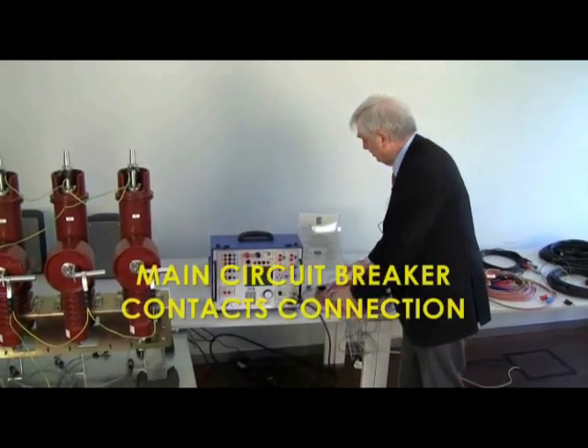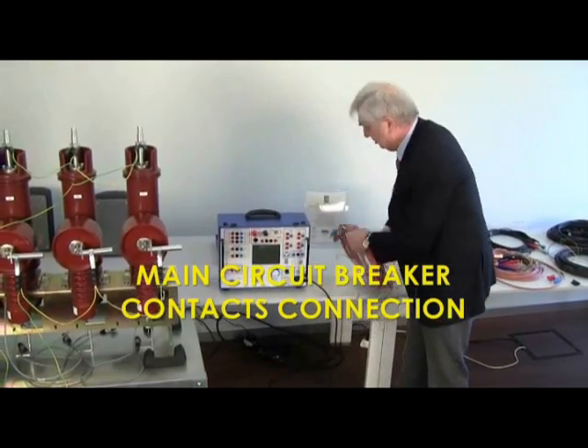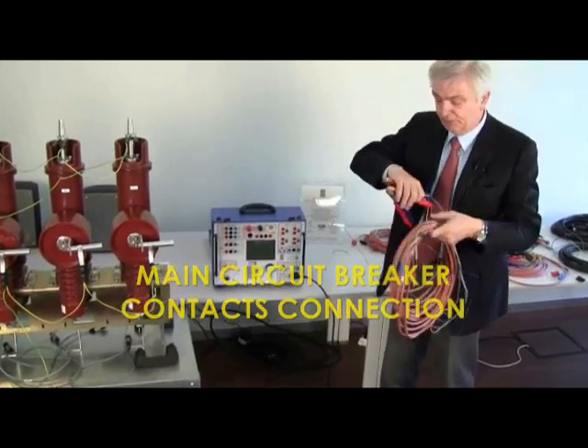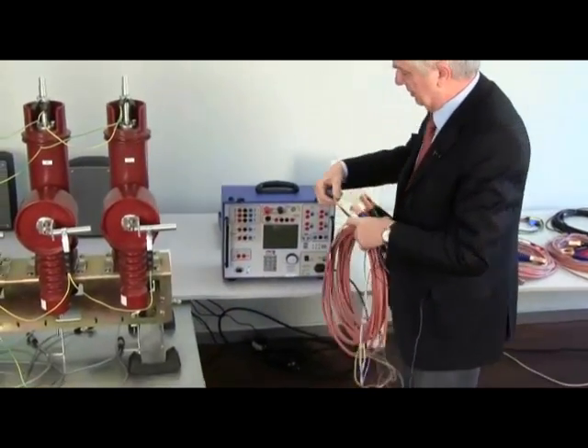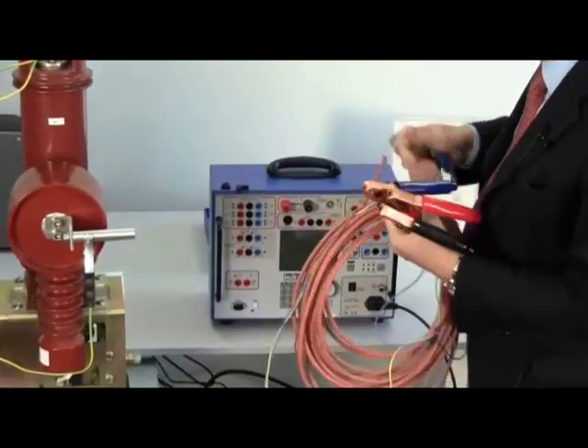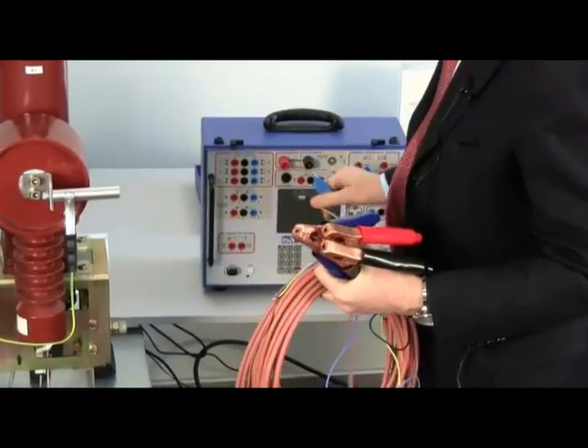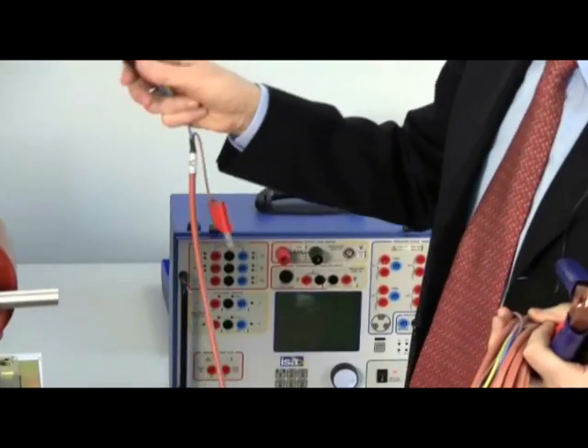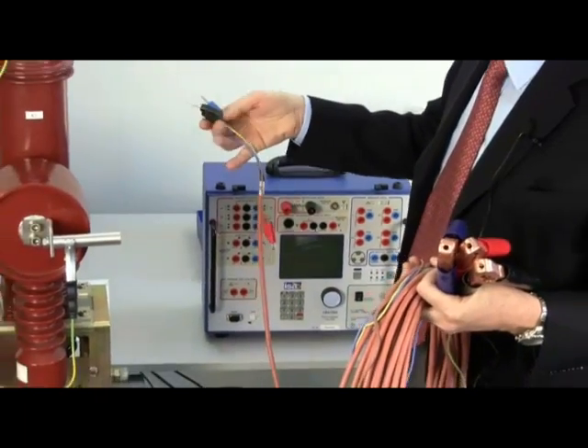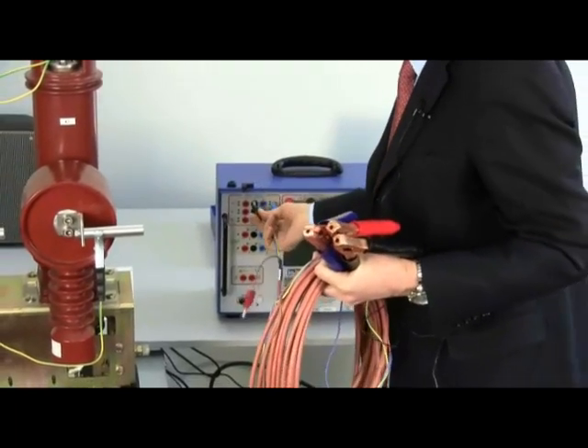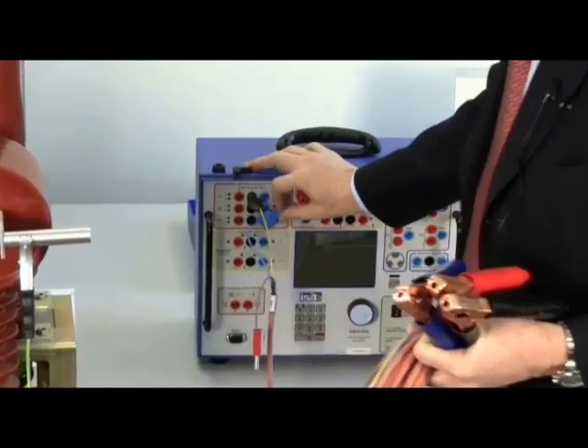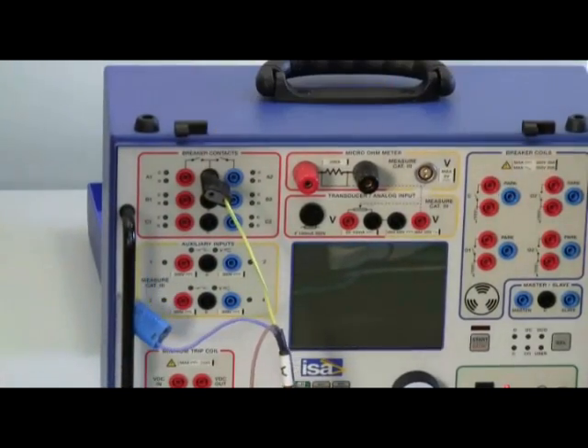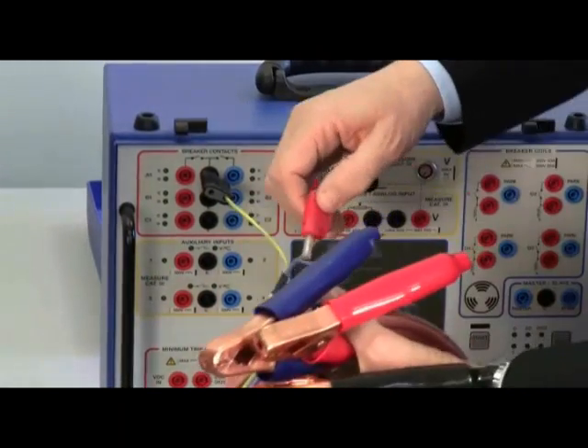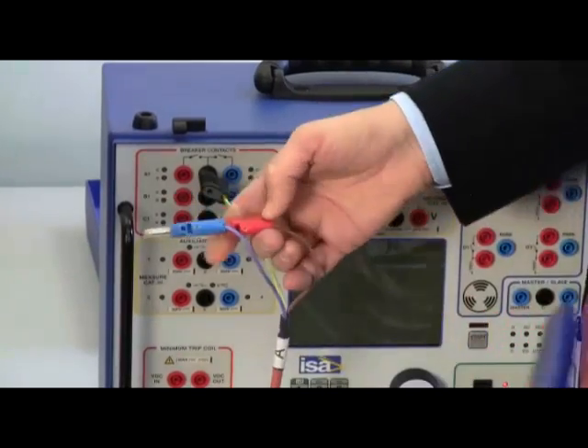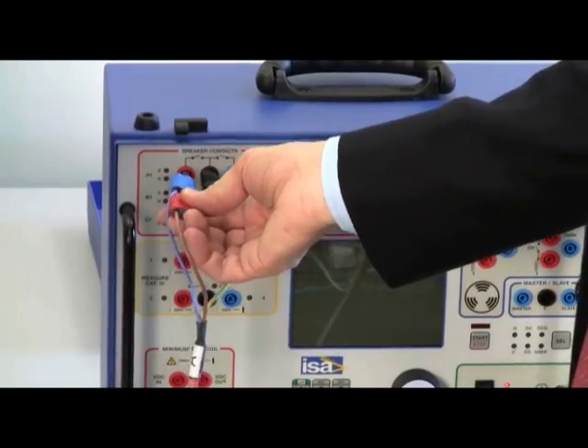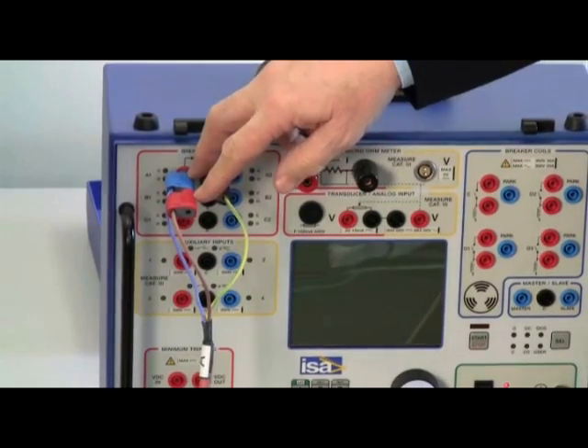Now I start connecting the main circuit breaker contacts with the cable provided. Of course, cables have always the attitude to mess up. Now I have a one-pole circuit breaker, while the cable is foreseen for 2 poles. What I do is to connect the black, for instance, to the central position here, while the other 2 contacts I could leave one open, but I prefer to connect them together here, red and blue.